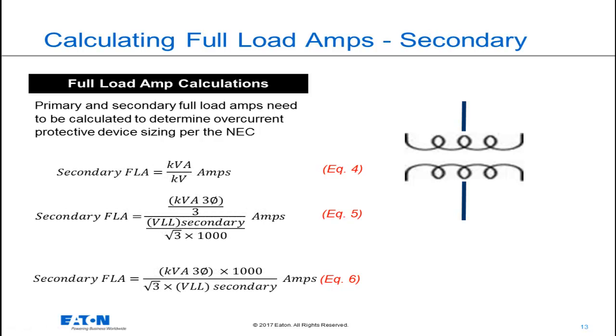Calculating the secondary full load amps is very similar to how we calculated the primary full load amps. The difference is that I'm using the secondary voltage instead of the primary voltage in the standard equation. So we have the three-phase kVA times 1,000 over the square root of 3 times the secondary line-to-line voltage. That gives us the secondary full load amps.